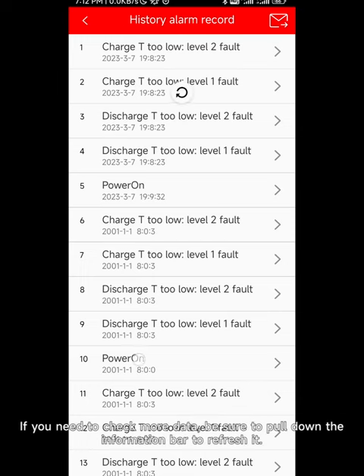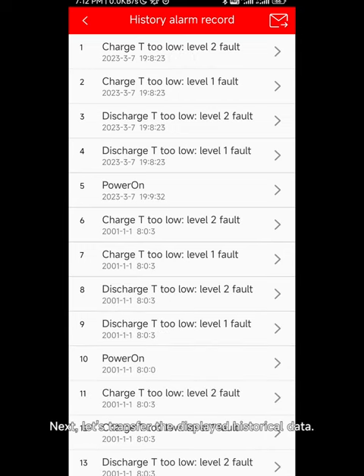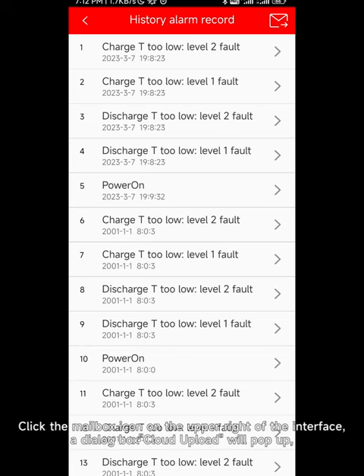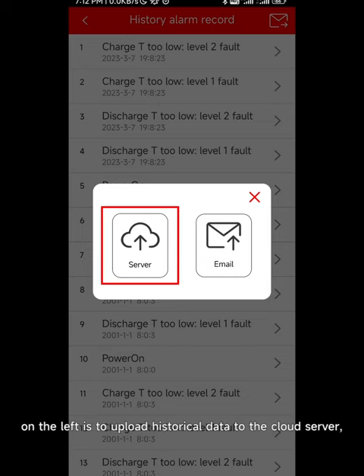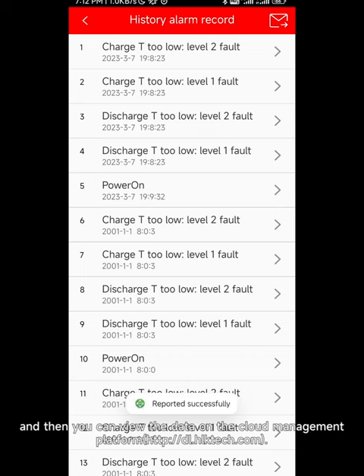Click the data reporting column to enter the historical alarm record interface. The interface displays recent historical data. If you need to check more data, pull down the information bar to refresh it. To transfer the displayed historical data, click the mailbox icon on the upper right of the interface. A dialog box will pop up — on the left is to upload historical data to the cloud server, where you can view the data on the cloud management platform.